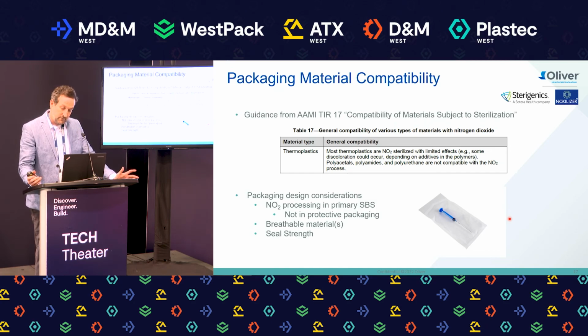Seal strength, you want to look at seal strength in any application. You want to have it high enough to be above your minimum peel strength, low enough to be open and usable by the end user in the sterile field. There's not a lot of vacuum in this process, but you want to make sure that you're really looking at a validated process when you look at the NO2 sterilization process.